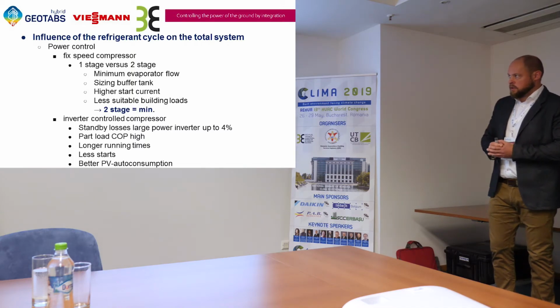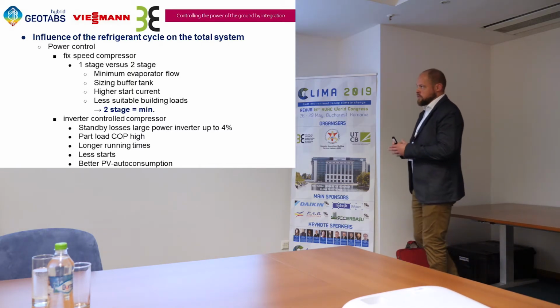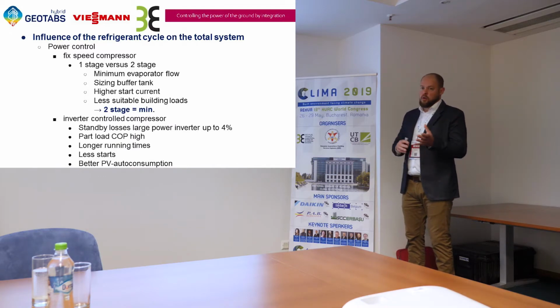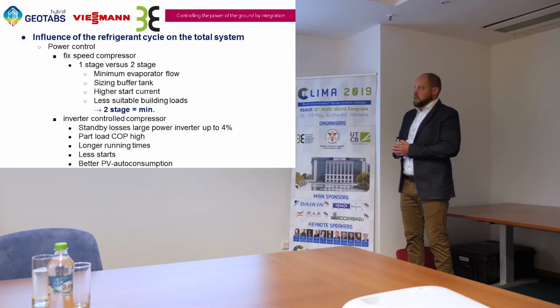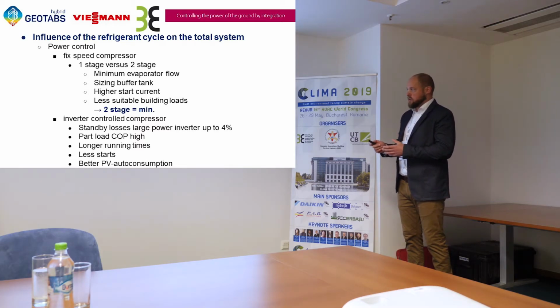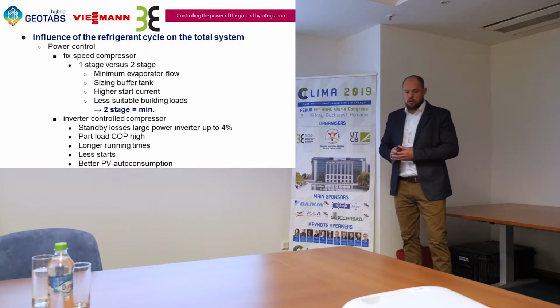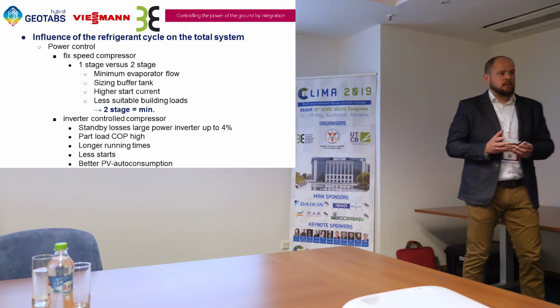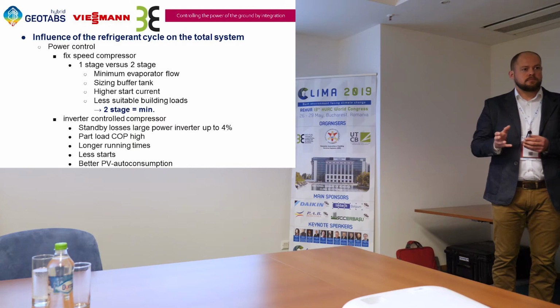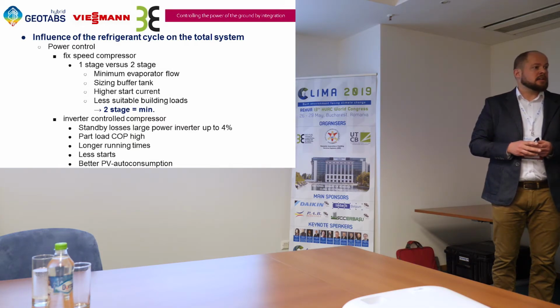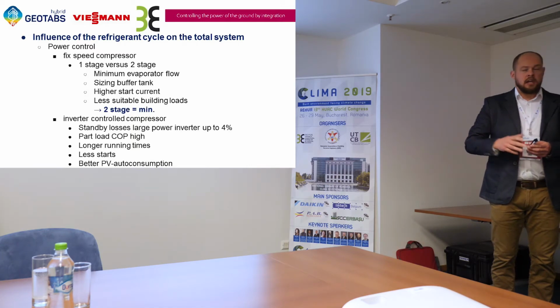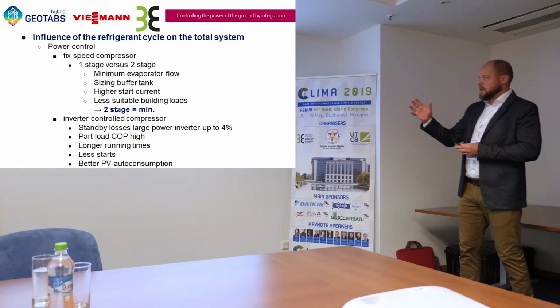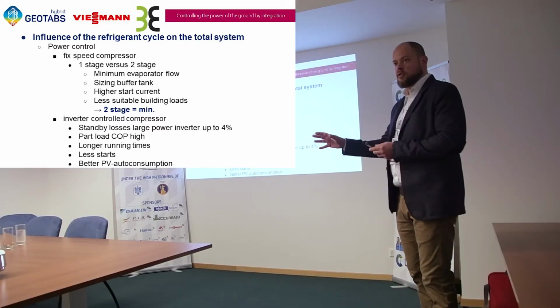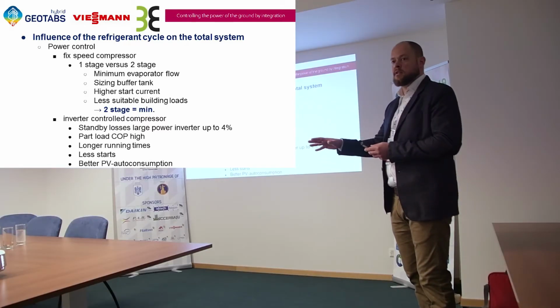So I talked a bit about power control. You have a system with fixed speed compressors. You can have a one-stage or two-stage compressor. You keep in mind the minimum evaporating flow with the two-stage system, and also the sizing of the buffer tank is important. Normally, when we size a buffer tank, we use 20 liters per kilowatt. So if you have a 100 kilowatt heat pump, you have about 2000 liters of buffer tank. If you have a two-stage compressor, you can select the buffer tank on the minimum stage, so the lower stage of about 50 kilowatts, for example.